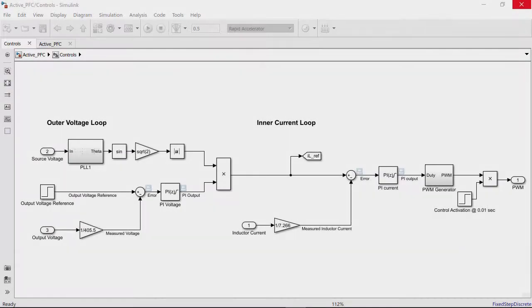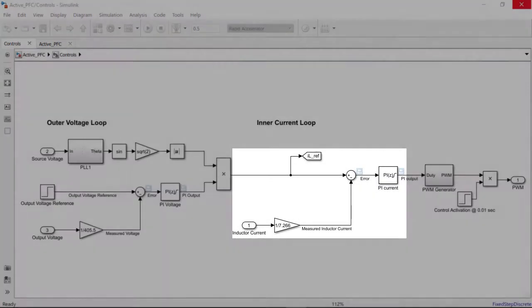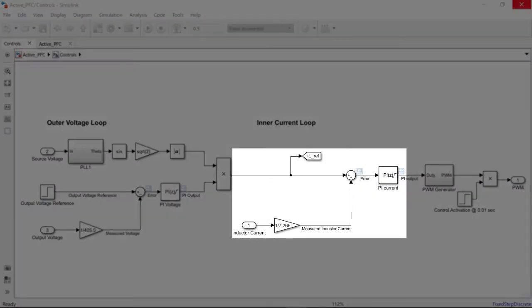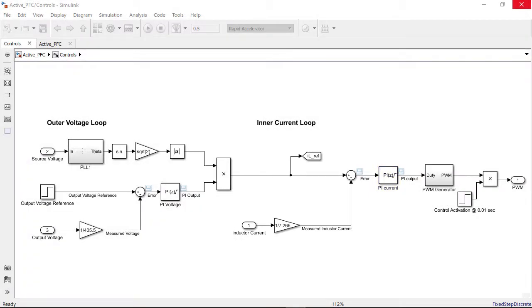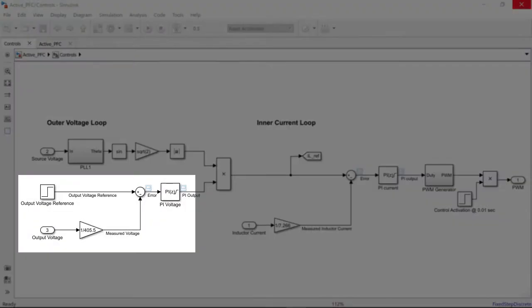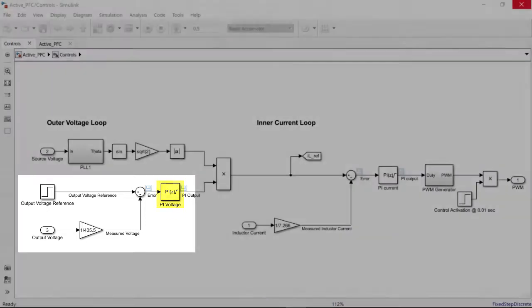Our workflow will be the following. We will first tune the inner loop to obtain the optimal PID gains for the current loop. With the inner loop tuned, we will tune the outer voltage loop to compute gains for the voltage loop PI controller.